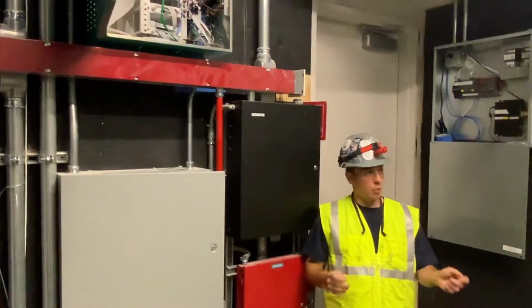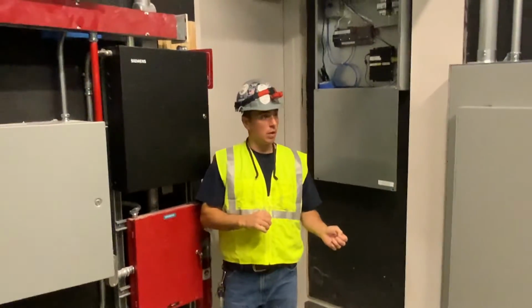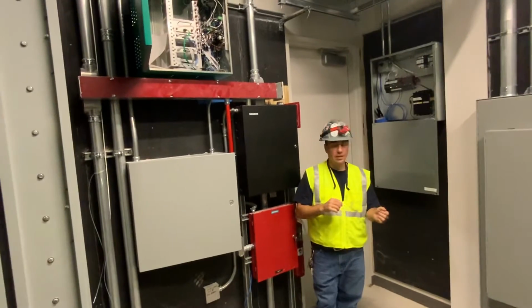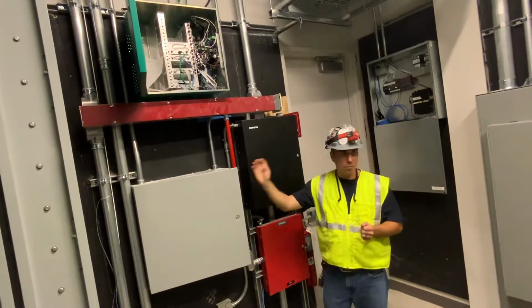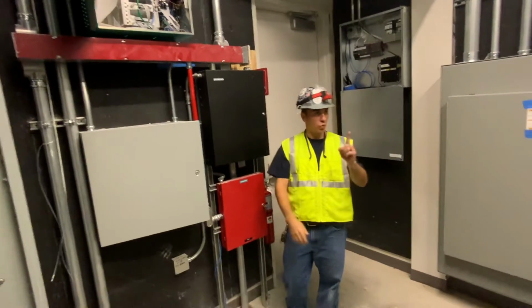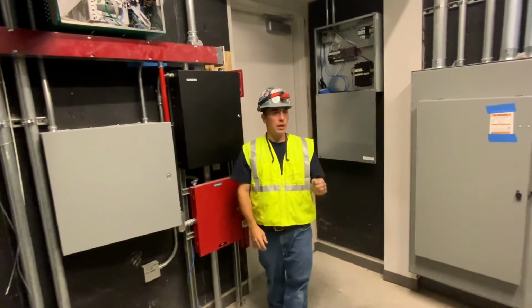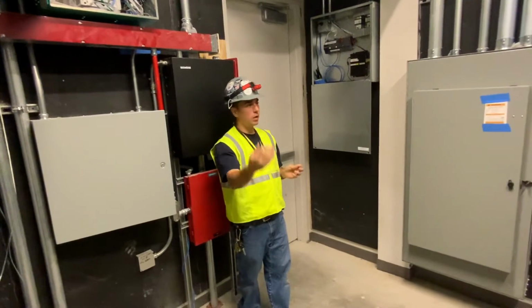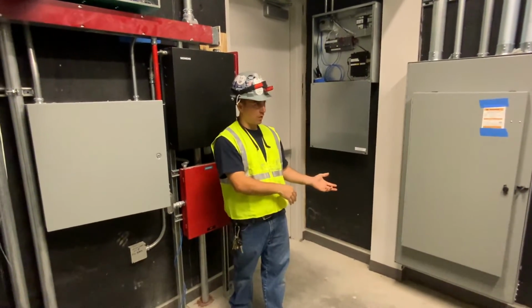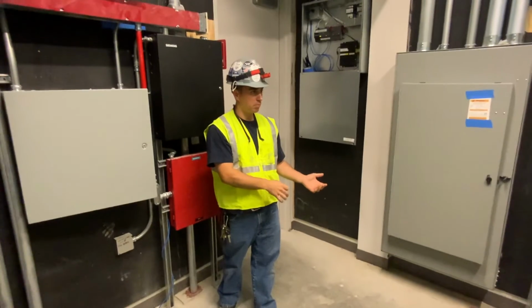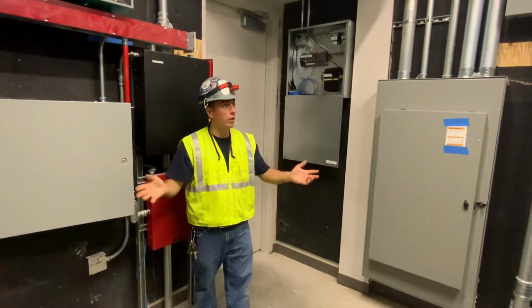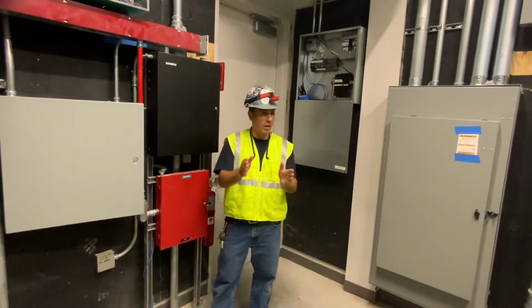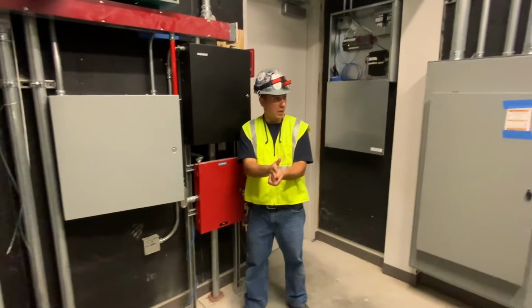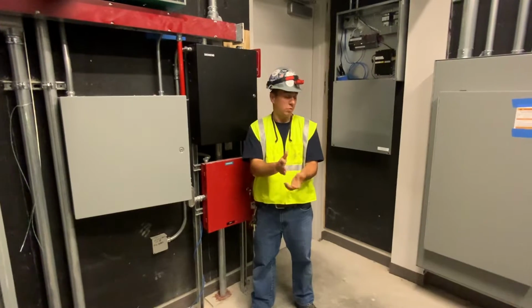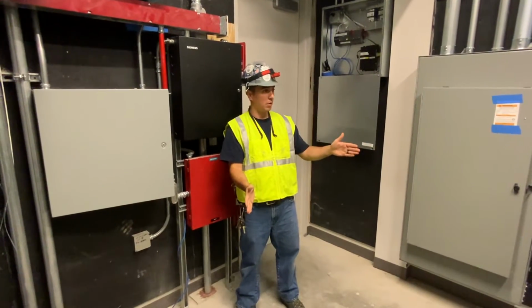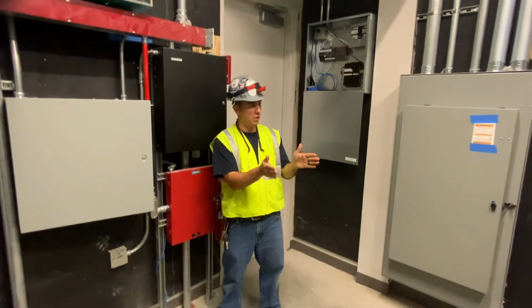So the way that it would work for being able to increase your indoor air quality command, the IAQ command that you have in Phoenix, is sampling your different rooms, and then there's one supply air sensor. So instead of just saying, I want it to be less than 700 parts per million on my CO2, or whatever the different parameters. You have different parameters for TVOC. Instead of just saying this is what I want for the CO2 specifically, you can compare it to the supply. So it's saying we look at what the difference is between the two.